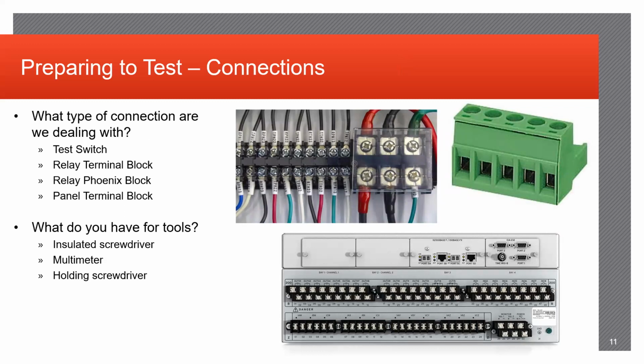Preparing to test and your connection setup. So again, after isolation, usually you'll identify the points where you need to hook up your test set. Going back to what we discussed last Thursday, those knife switches associated with the relays usually are the easiest source. The first step is to correctly identify that each point of the test switch lines up with the port on the relay. Once that's identified, you can usually hook up a paddle or alligator clips, if need be, from the test set to the knife switches.